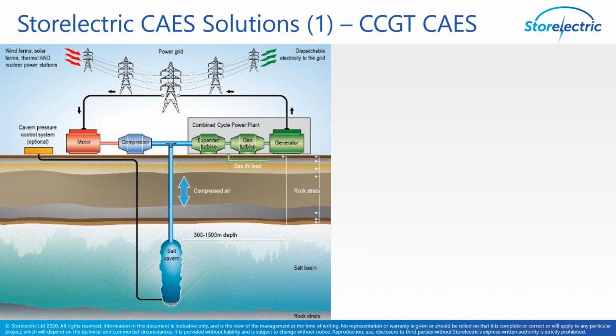The first solution we developed—the challenge with compressed air energy storage isn't to do with the air. The way it works is that when you have surplus or cheap electricity on the grid, you use it to compress air, which you store underground because that's the only place big enough. When you need the electricity again, you let it out to blow a turbine and regenerate electricity. The challenge isn't doing the air—that's been done for decades. In fact, about a third of natural gas storage in Europe is in salt caverns, very similar salt caverns. The challenge is what you do with the heat.